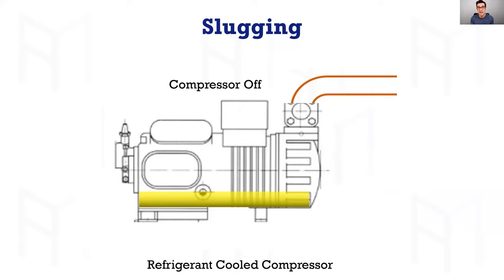This is what happens: the compressor was off, it starts, and then bam — you're breaking pistons, breaking rods, breaking discharge and suction reeds. If you pull off a head and there's a piston full of oil, that's usually from a flooded start. In the 4D and 6D Copeland compressors, there are venturis — crankcase vent valves inside them — and during a flooded start it blows oil and liquid refrigerant up through those.